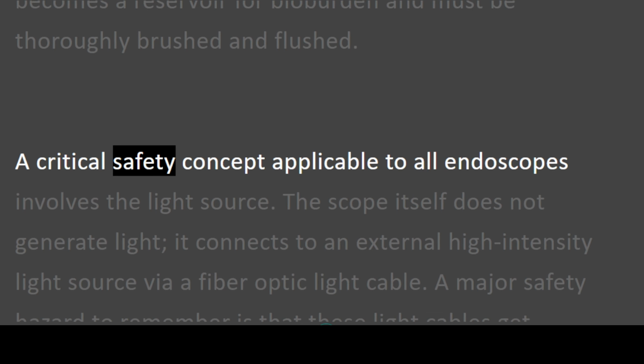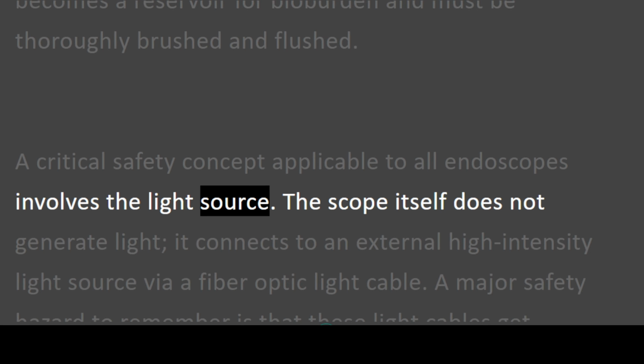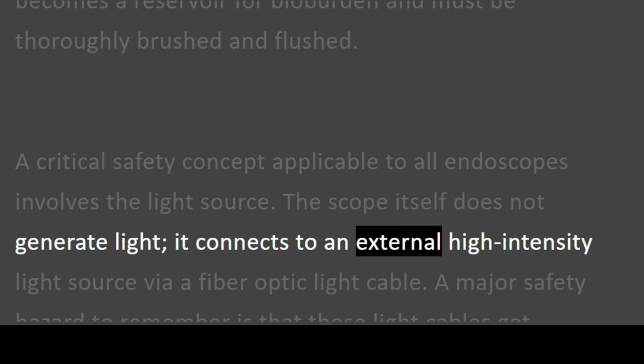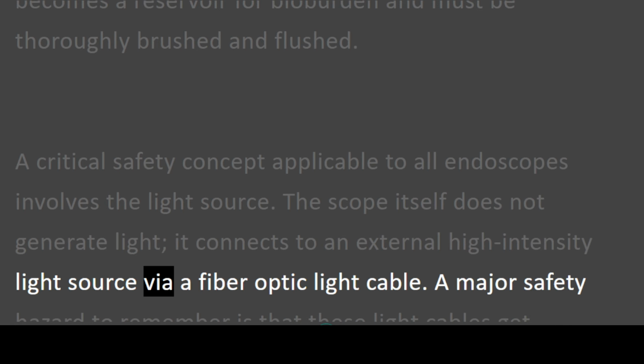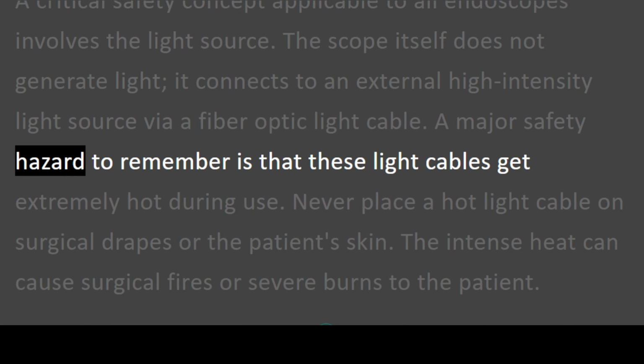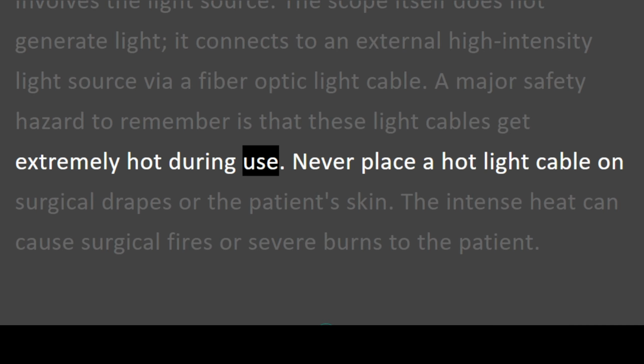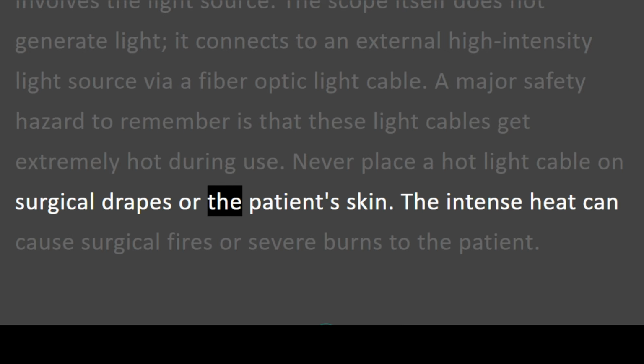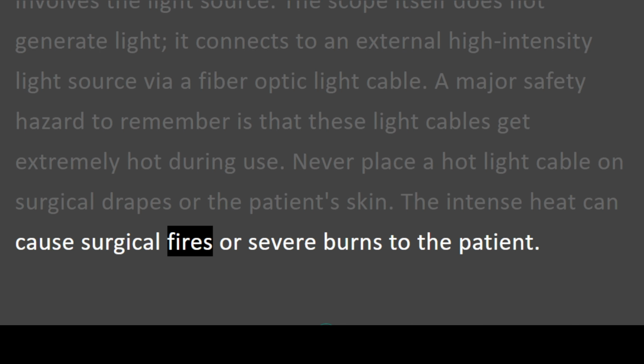A critical safety concept applicable to all endoscopes involves the light source. The scope itself does not generate light. It connects to an external high-intensity light source via a fiber optic light cable. A major safety hazard to remember is that these light cables get extremely hot during use. Never place a hot light cable on surgical drapes or the patient's skin. The intense heat can cause surgical fires or severe burns to the patient.